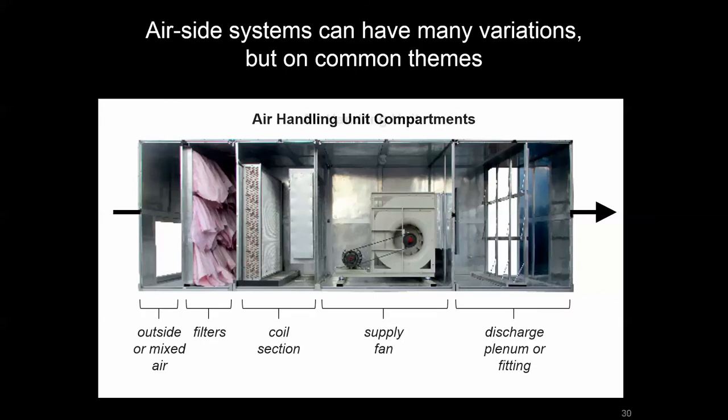This is what it might look like on the inside. There will be many variations, but typical components include: a chamber or plenum where outside air comes in and possibly mixes with recirculated return air; filters designed to protect equipment such as coils and fans, as well as provide air filtration for indoor environmental quality; a single coil or combination of coils for load management with that mixed air; a supply fan — in this case a belt-driven squirrel cage or centrifugal fan — and then a plenum or fittings to connect to the main supply duct.